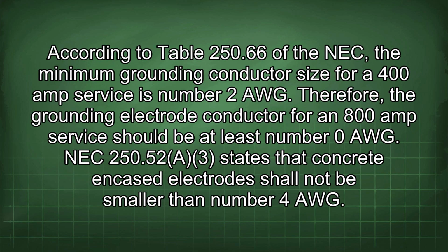According to Table 250.66 of the NEC, the minimum grounding conductor size for a 400 amp service is number 2 AWG. Therefore, the grounding electrode conductor for an 800 amp service should be at least number 0 AWG.